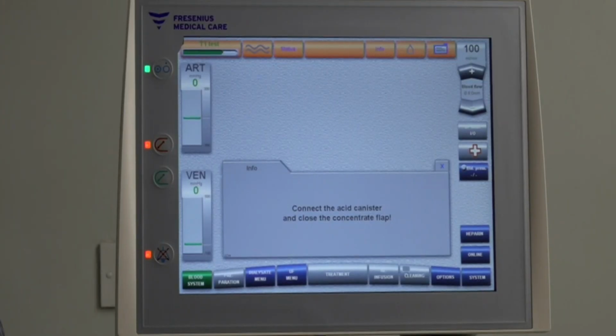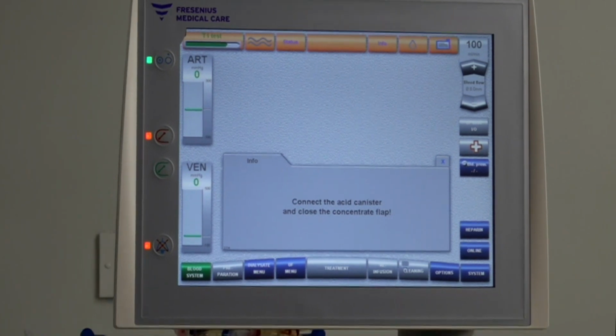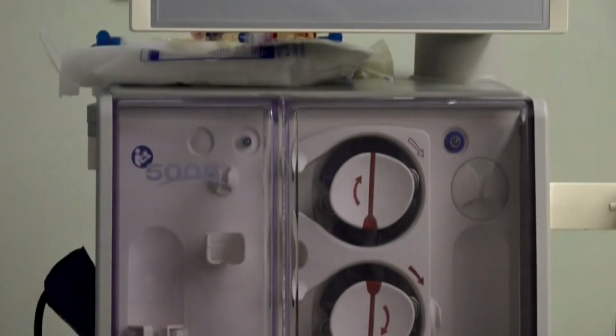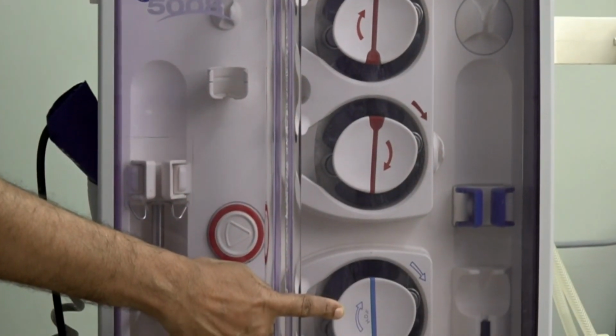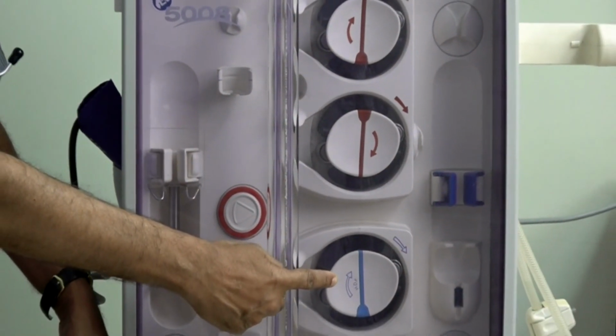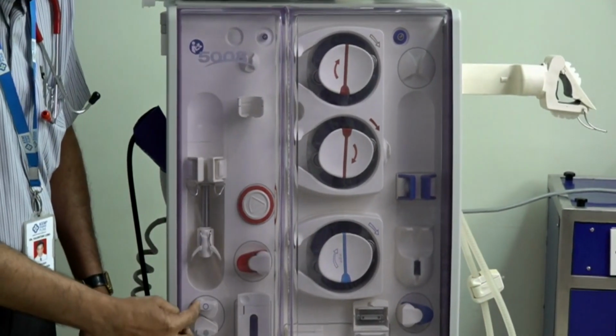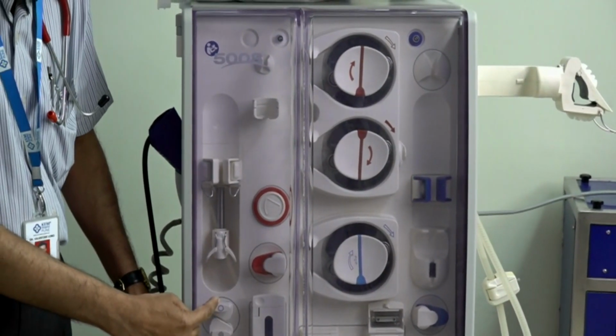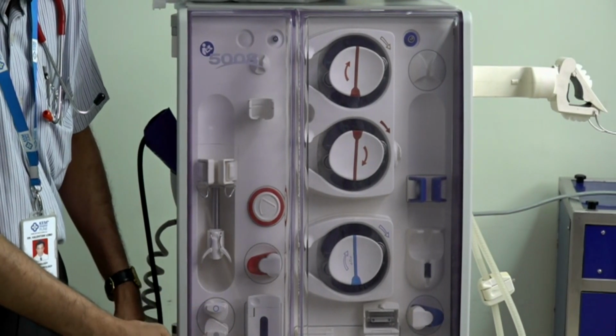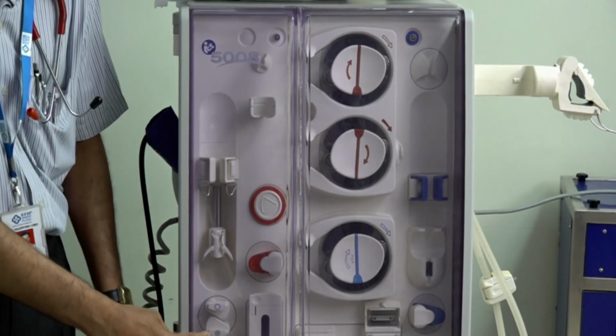We are going to perform an online hemodiafiltration on the Fresenius 5008 machine. As you can see, the machine has a very user-friendly interface with a touch screen. Its menus, the dialysate menu, the ultrafiltration menu, and the online menu are here on the main screen. It also has, in addition to the blood pump, a substitution fluid pump which will deliver the sterile substitution fluid, and the substitution fluid is obtained from the substitution port here on the machine, and the prime is dumped to the rinse port of the machine.